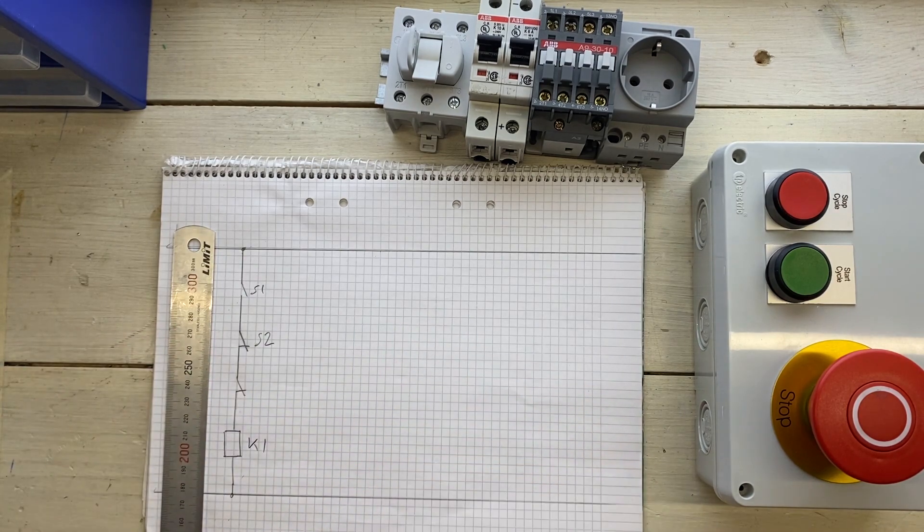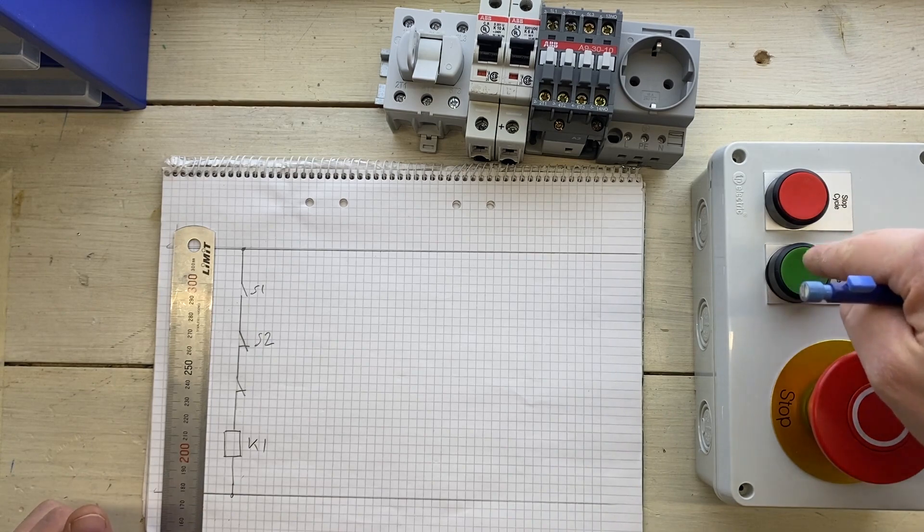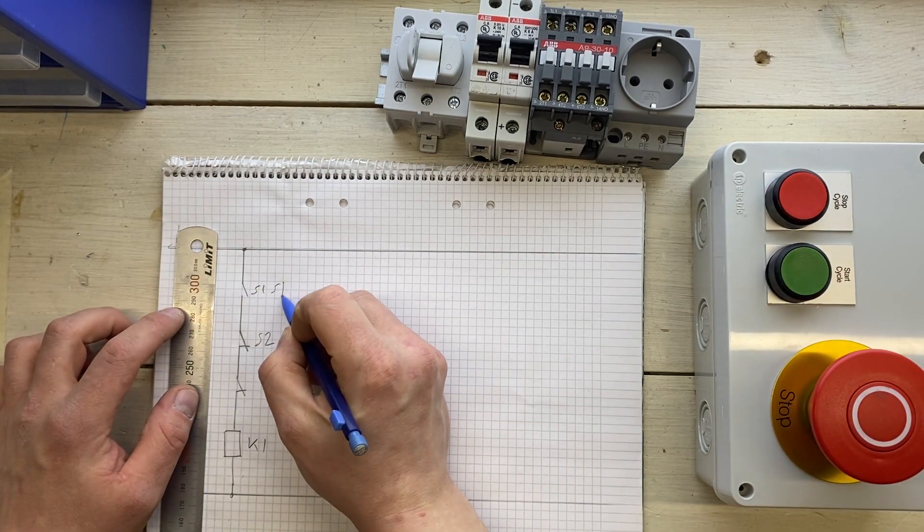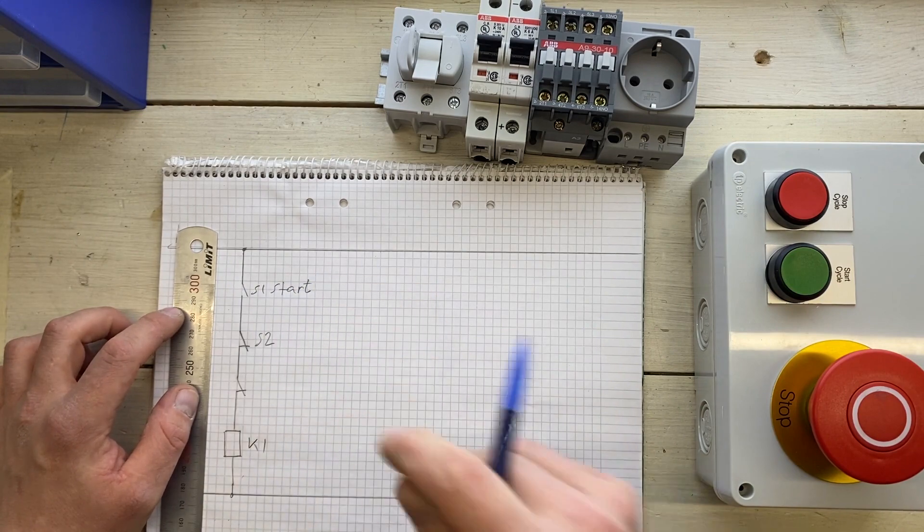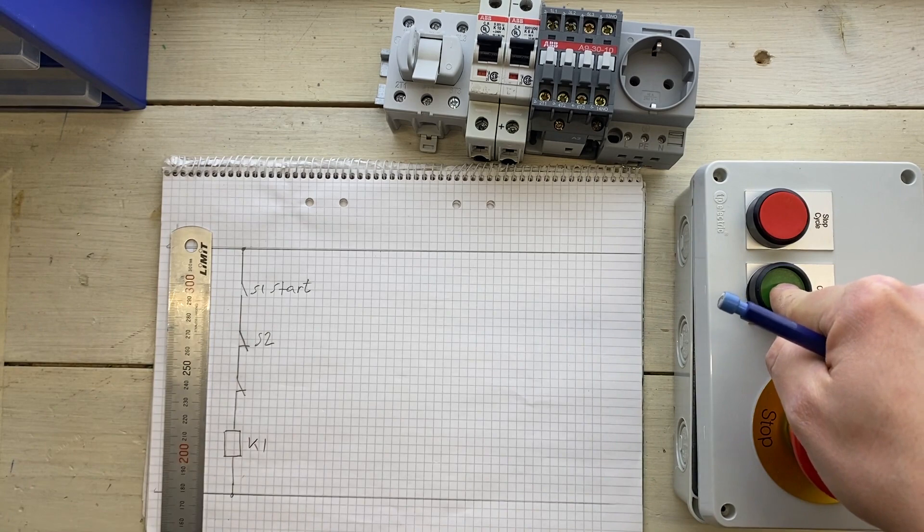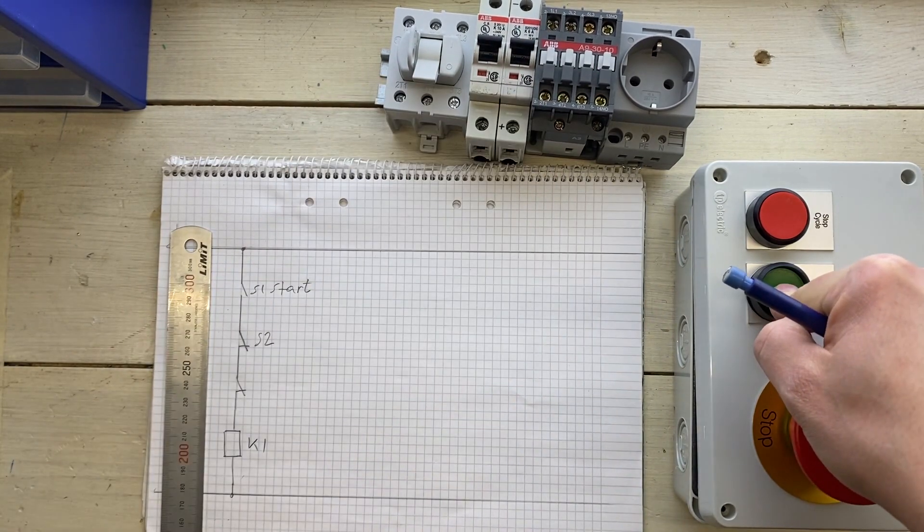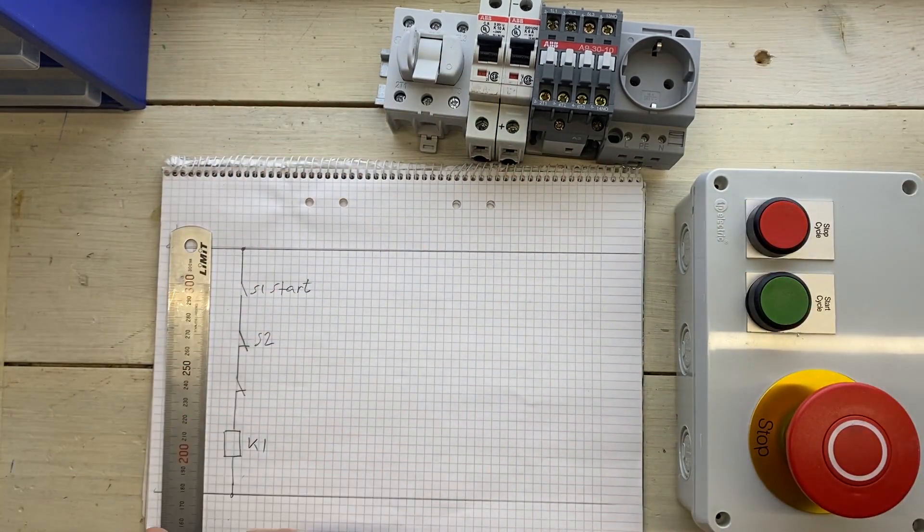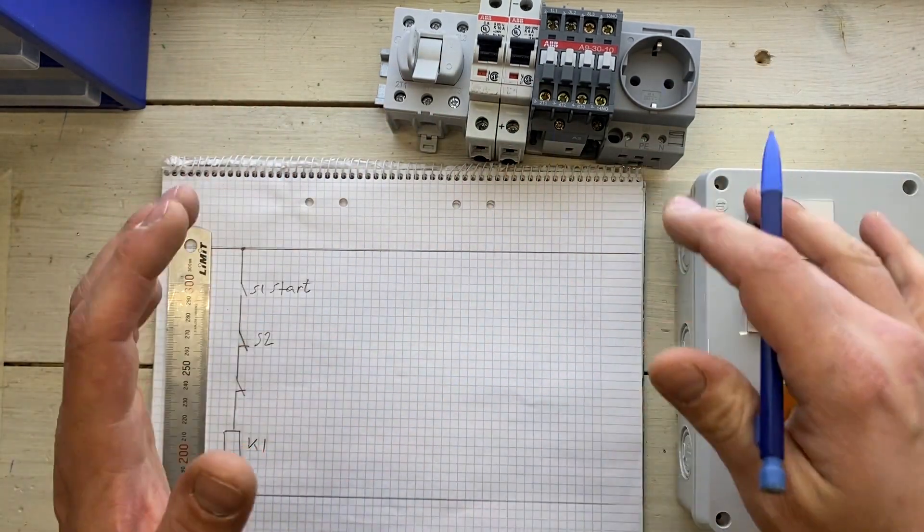That's for pulling the contactor and closing the circuit. We can name this one K1. So this is our first step in the layout. So what will happen here is that when we push the start cycle button, the start switch will close and the contactor coil pulls and this one closes. But as soon as we release this button, the contactor will open again. And that's not what we want, we want it to hold itself.